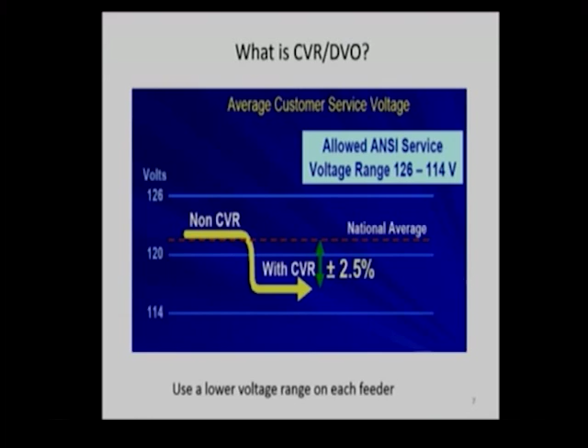So what is CVR or DVO? As I mentioned, most utilities operate in the high range of the voltage level, so that they don't have low spots on their grid they don't know about. With CVR and the adaptive controller I'm going to talk about, you can lower that voltage level and save energy, reducing all of the customers' energy bills.